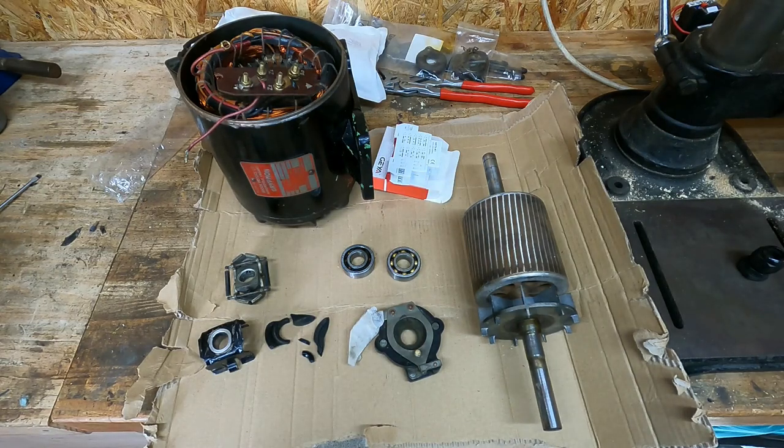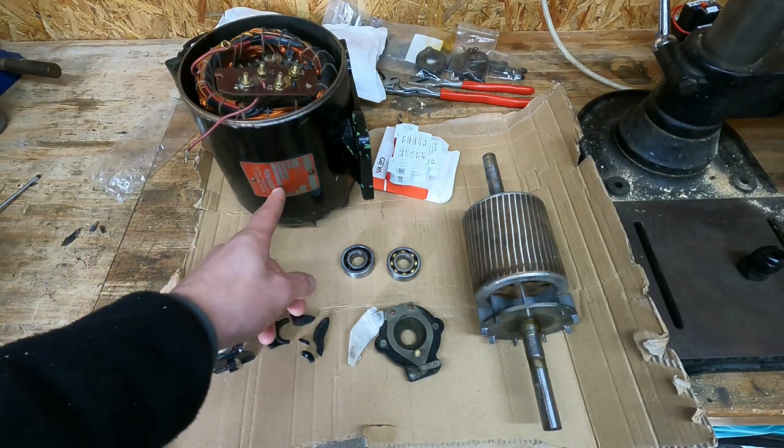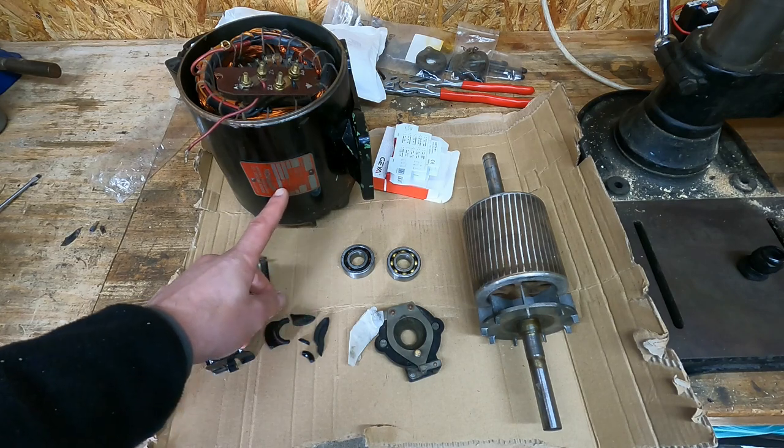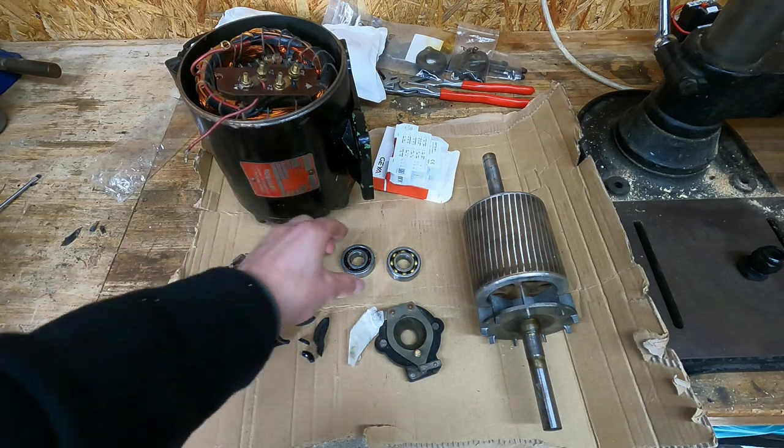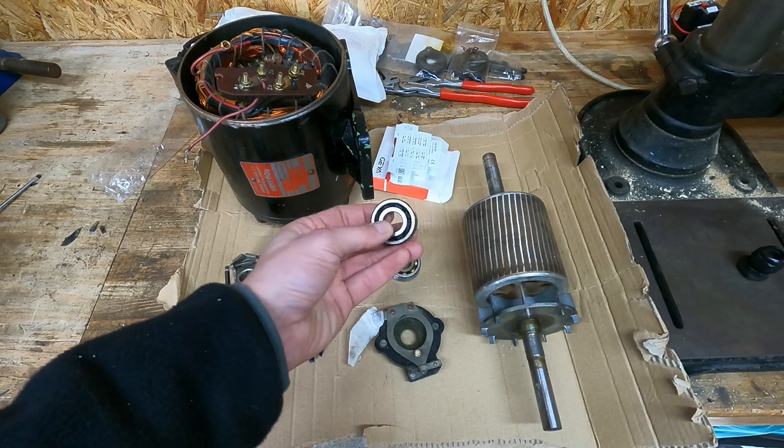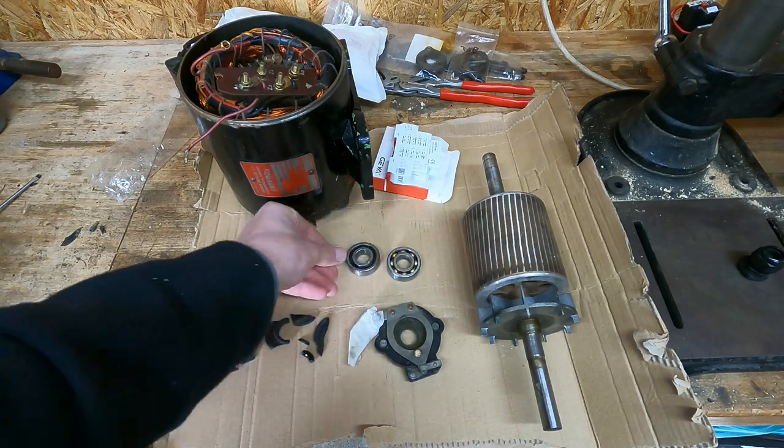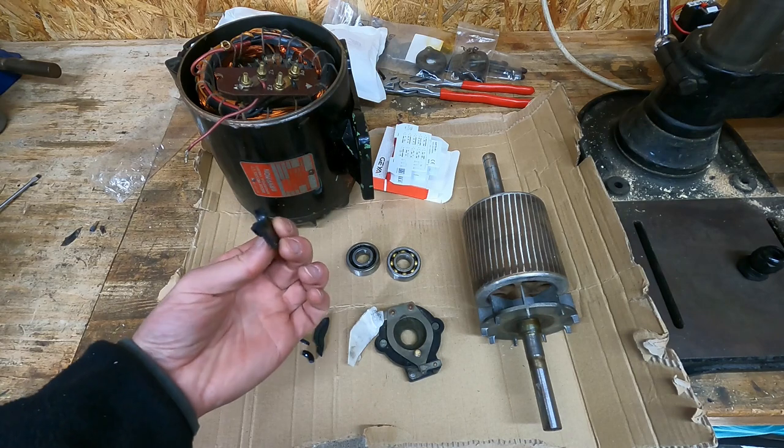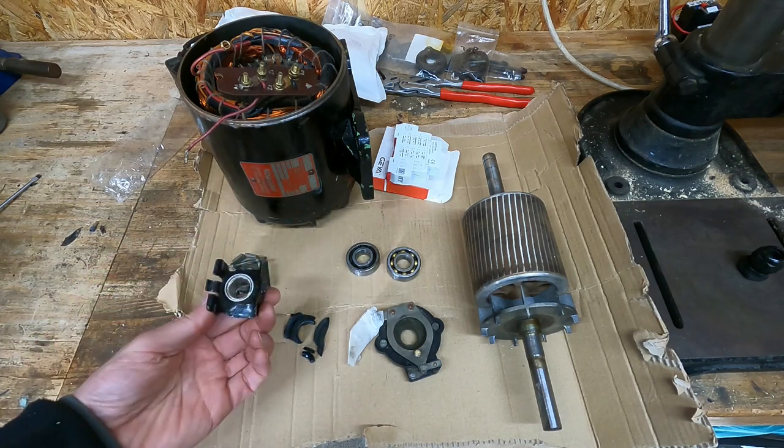Hello and welcome to the workshop. Today I'm working on this Brook Crompton single-phase induction motor. I'm replacing the bearings because they are full of old grease and they're cooked. But unfortunately, when I was taking the motor apart, I managed to break the centrifugal switch.